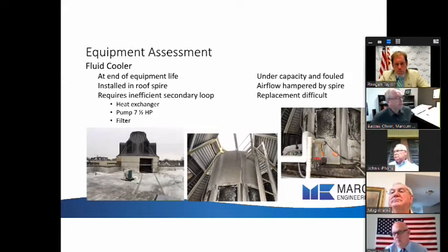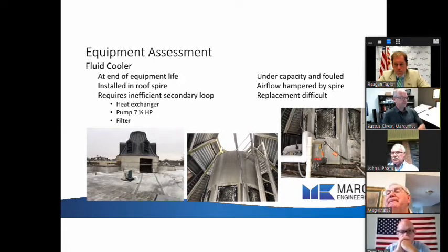First piece of equipment was a fluid cooler. This is on the roof. This is what helps provide the cooling necessary for the system. What I noted about the fluid cooler is that it is at the end of its equipment life. 15 years is what we estimate these units can make it. We've made it 15 years. It's under capacity and it's fouled. Those pictures you see to the right and of the calcium buildup tell me that there's fouling going on, so the heat exchange is not complete. So I believe we're under capacity just due to the wear and tear and degradation of the unit.